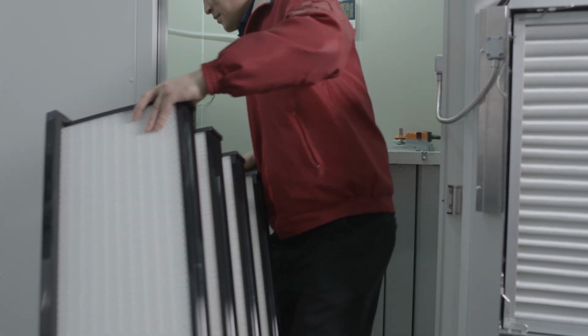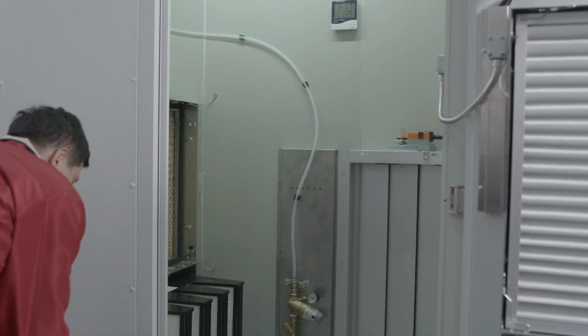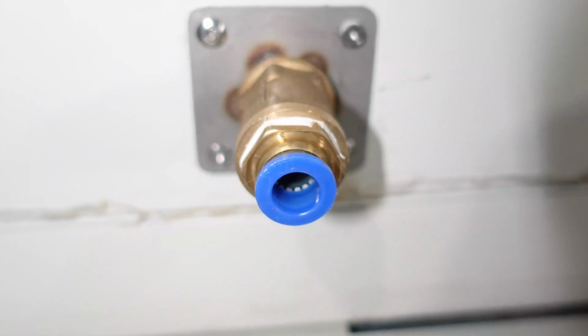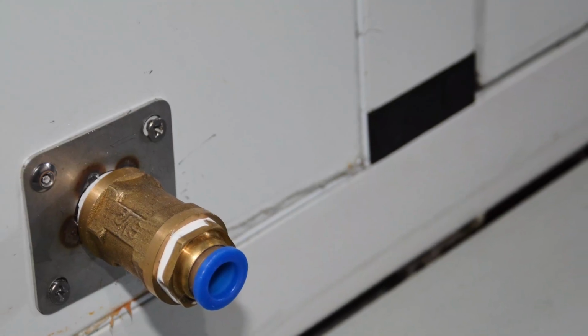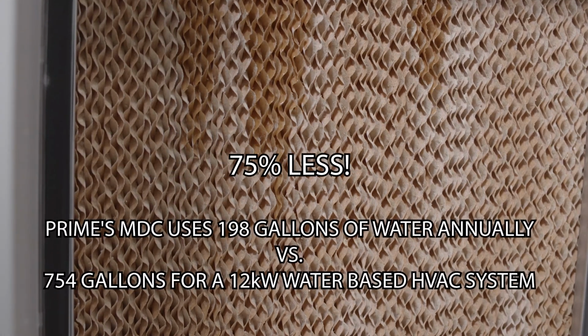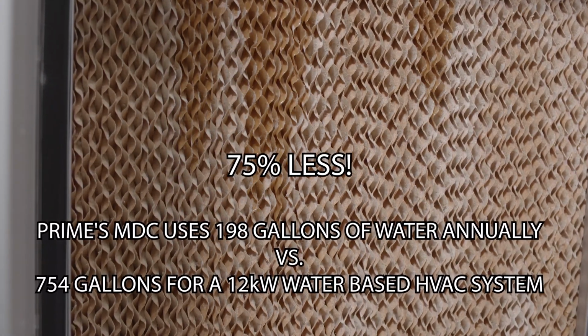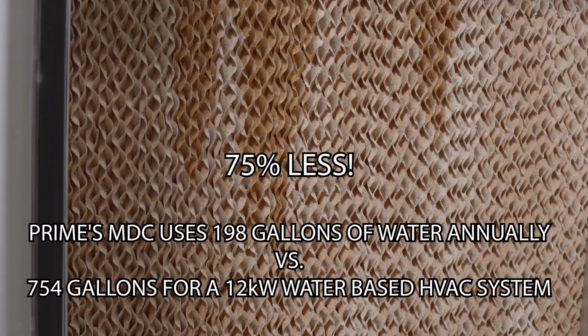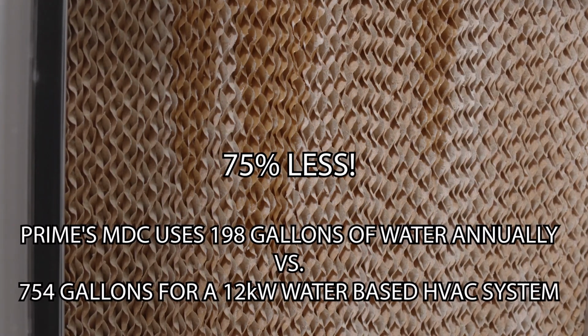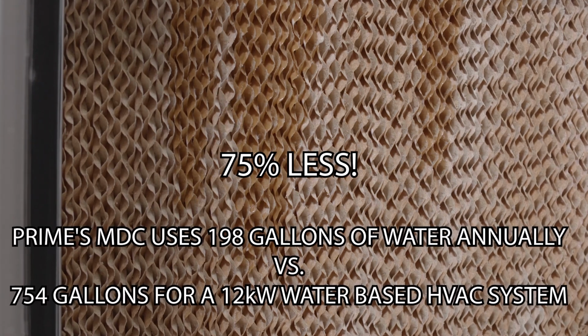Behind the F8 chemical filters is the evaporative panel. You'll need to have a water source, but the connection that's built into the MDC is standard, so it's easy to connect. Moisture comes through to the panel from outside the MDC via the universal 1/2-inch connection, just like a typical garden hose. The supplemental evaporative cooling uses approximately 1/4 of the amount of water required for traditional water-based HVAC cooling methods, either built into a data center or as an external supplemental unit, again, saving money and the environment.